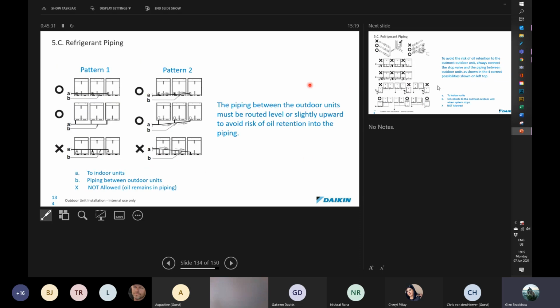All right. Inside the manual, you also find that it gives you some patterns for installing piping. The ones with a 0 are the ones you may adhere to. That's what you're expected to install. Here you'll see the piping can be level with the intake. It can come underneath the unit. You can even slope it up, a slight slope, but horizontal is perfect. You may not bring it in above the height of the service valve. The reason is that the oil, again, will tend to fall out into the first unit. So just be aware of that.